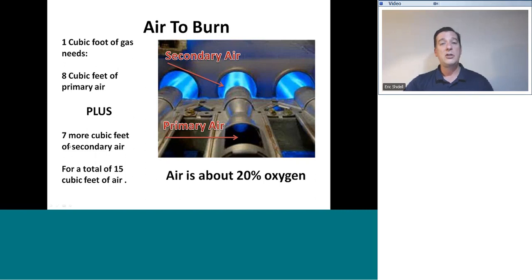We need an additional 7 cubic feet of secondary air. And a good question to ask is, Eric, if the 8 cubic feet of primary air contains enough oxygen to sustain the combustion, why do we need the additional 7 cubic feet of secondary air? That's a good question. That additional 7 cubic feet joins the flame already in progress at the end of the flame down here. So there's more air traveling in and being drawn into the combustion process naturally in this direction.